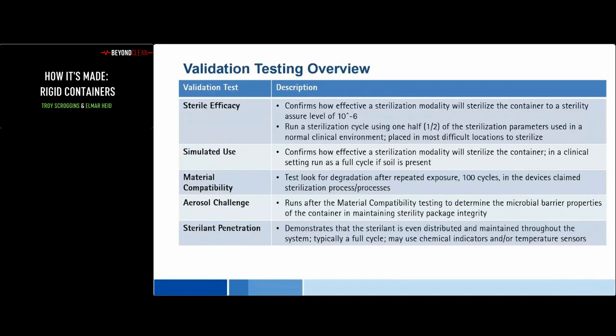Because containers are reusable, the material compatibility study is very important. This is a repeat study. The containers are usually run 100 times, to show that from the first cycle to the 100th cycle there is no degradation of the product itself. That test is really looking at wear and tear over time. It's usually followed up by an aerosol challenge, which is run after the material compatibility test and shows that the barrier in the container is still able to maintain integrity.